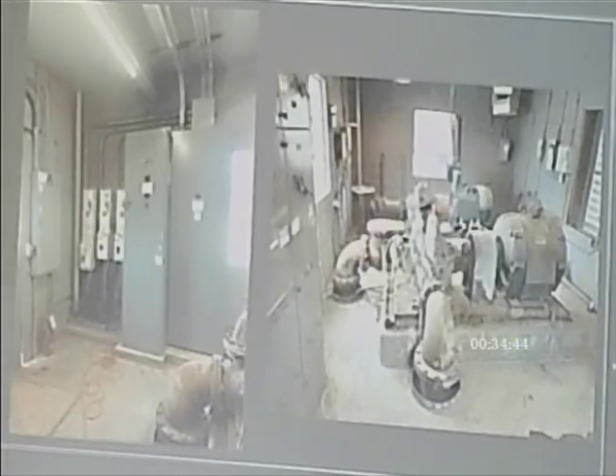These pumps have been in service for quite some time. But putting them on a VFD, making sure they're not on a cross-line start, makes a big difference, because you can start your pumps gradually and easily. It's not just a jolt. Whereas if you have cross-line starters on your pumps, you just hit it hard, and eventually it wears out harder on the bearings and things like that. So nice to have the VFDs in place. Plus it reduces the size of generator you're required to handle the full load amps when you start these big motors.